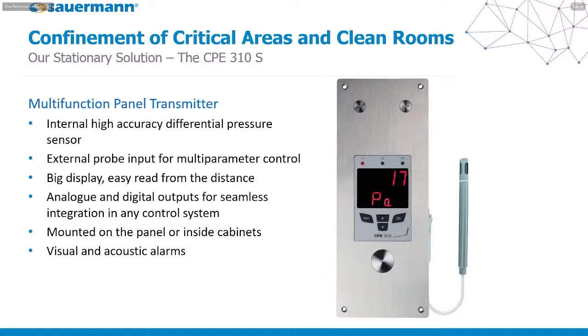In this case, the reason measuring differential pressure is very important is that you want to keep the pressure within that room greater than outside the room, because you don't want any contaminants coming into the room. Whenever you open the door for people to enter or exit the room, you want the air to move out of the clean room, not into it, because all the air coming into the clean room is already filtered very well. Obviously, that's the supply air coming in from your air conditioning or heating system. By measuring and ensuring that you have that differential pressure, where the pressure is greater in the clean room as opposed to the outside environment, you keep the contaminants out and keep the superior air quality within that clean room.